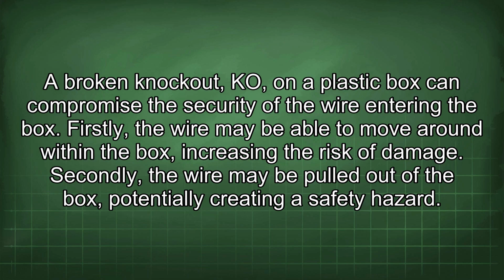A broken knockout (KO) on a plastic box can compromise the security of the wire entering the box. Firstly, the wire may be able to move around within the box, increasing the risk of damage. Secondly, the wire may be pulled out of the box, potentially creating a safety hazard.